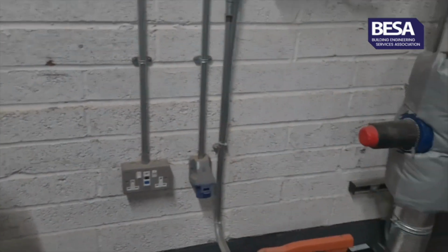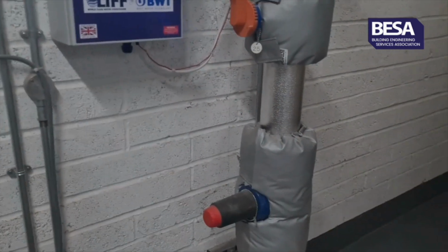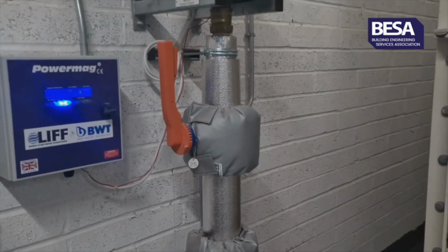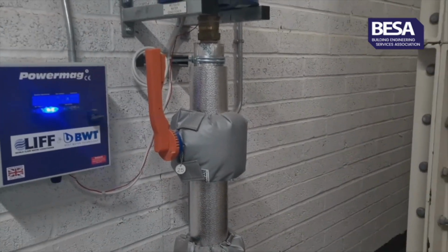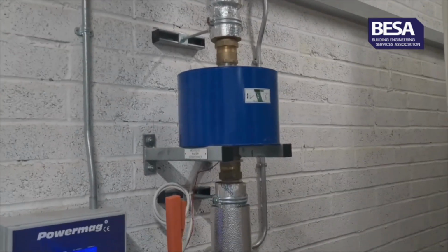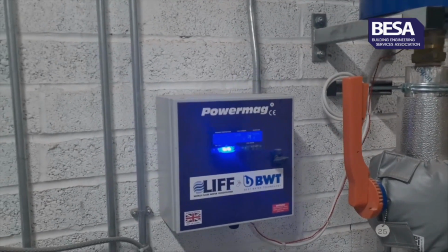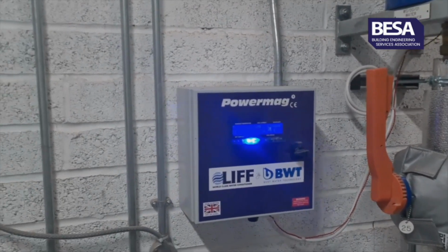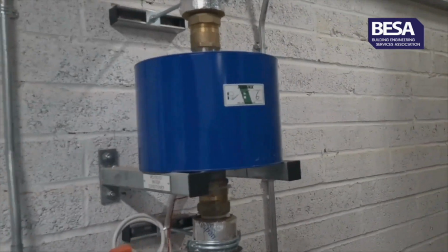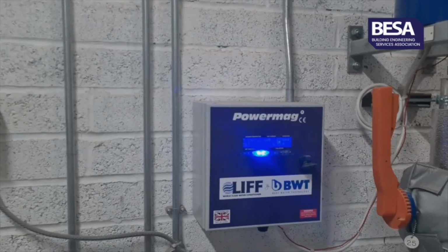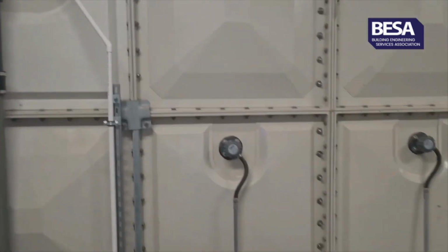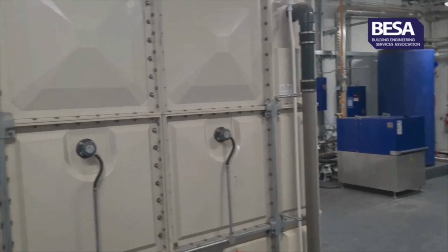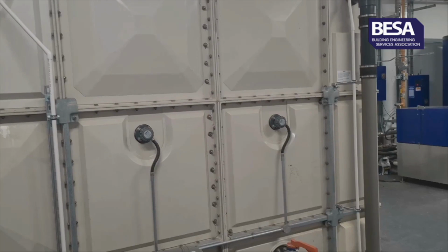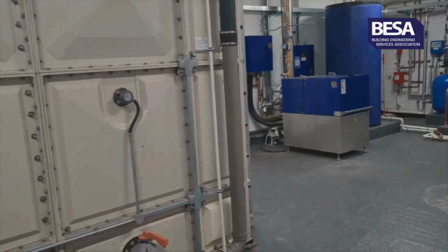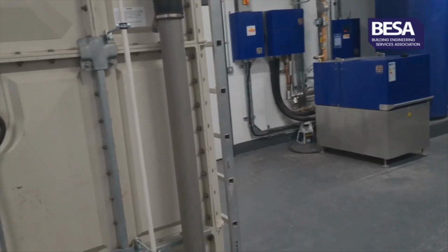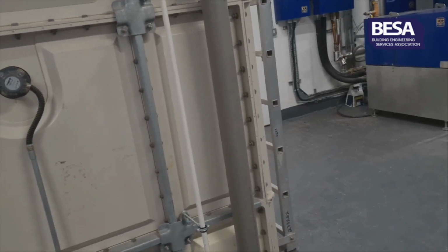So from the booster set, we then go through a PRV which serves the whole building. So this is actually the main boosted cold feed to the whole building. So 180 bedrooms in the hotel and the back of house areas as well. We've got an electronic water conditioner there, which is a Powermag. Again, the water conditioner has been fully commissioned by the manufacturer. You can see all working fine. And all the cold water has been chlorinated throughout the building, and also the incoming, for the connection made by Thames Water, to BS 8558, and lab samples and microbiological samples have all been taken and submitted, and that's all within the O&M manuals.